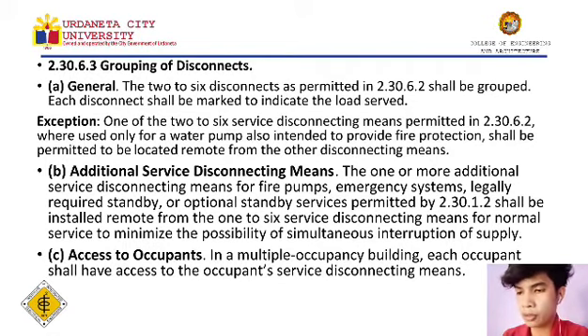Each building or structure must be provided with a service disconnecting means. It can be a single switch or circuit breaker, or up to 6 in a single enclosure or separate enclosures grouped in the same location. Exception: one of the 2 to 6 service disconnecting means permitted in 2.30.6.2, if used only for a water pump also intended to provide fire protection, shall be permitted to be located remote from the other disconnecting means.